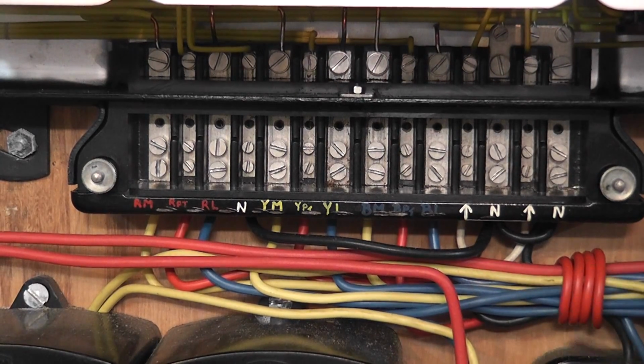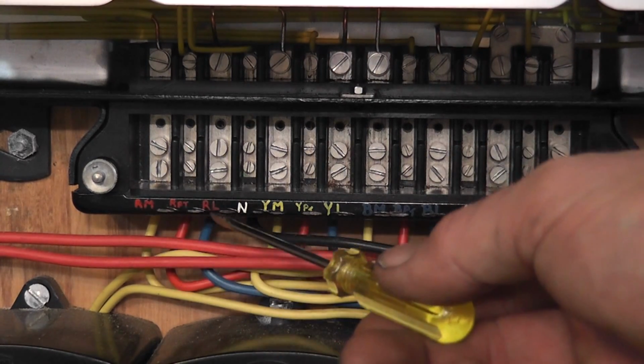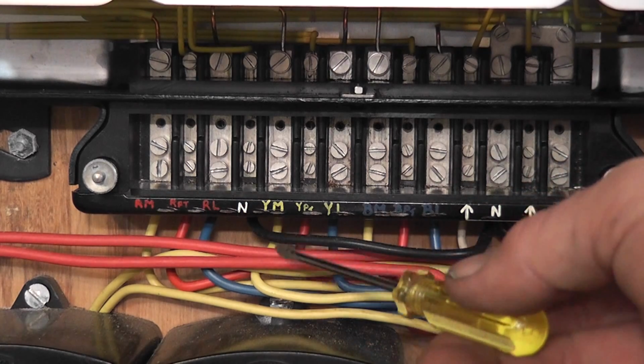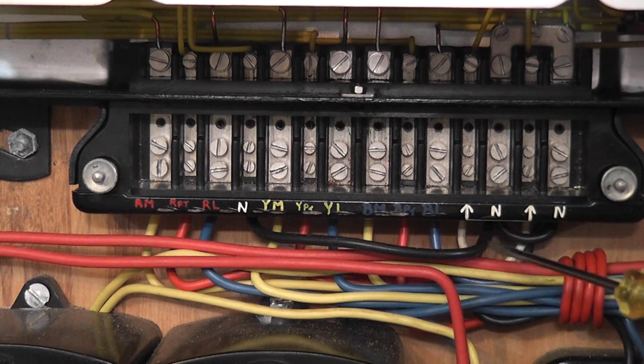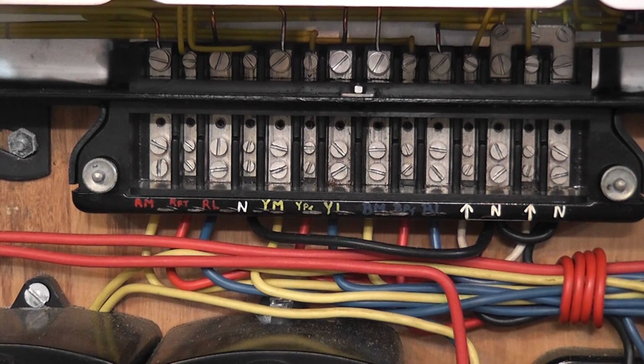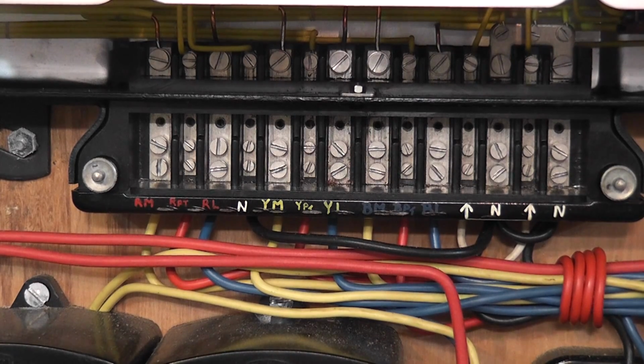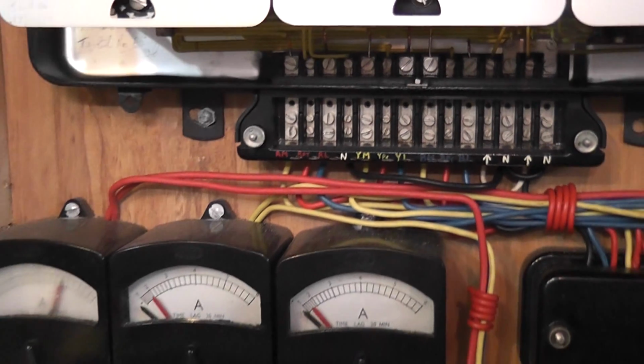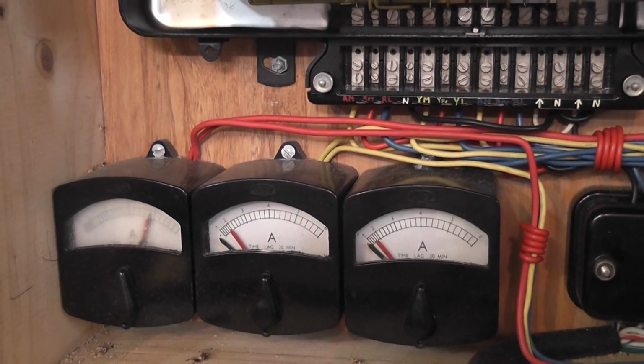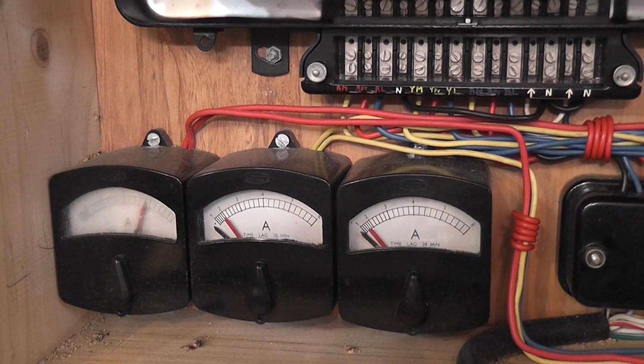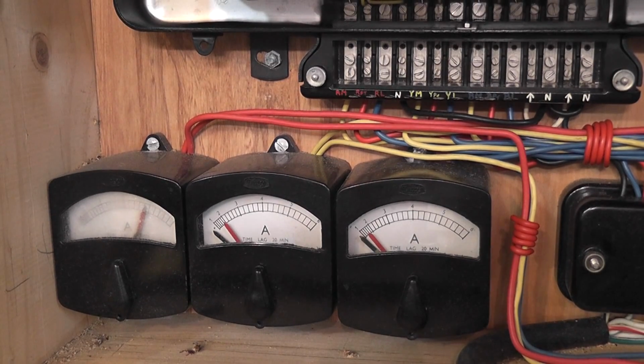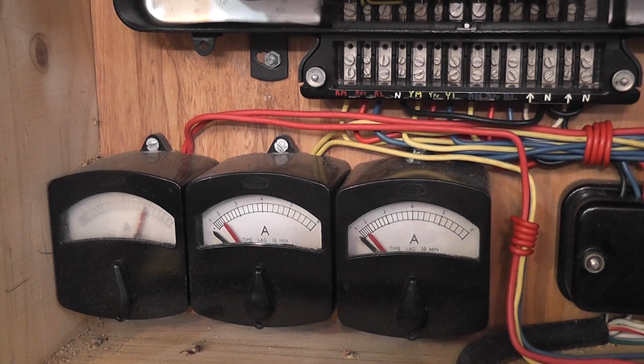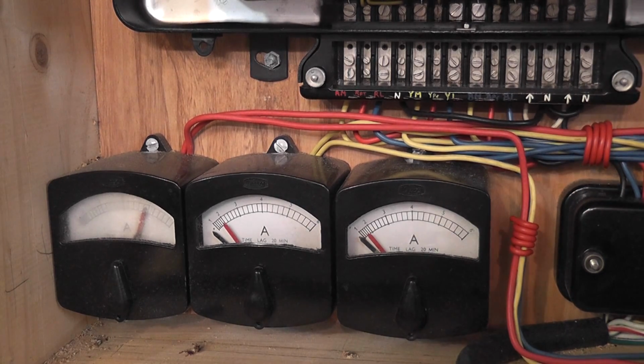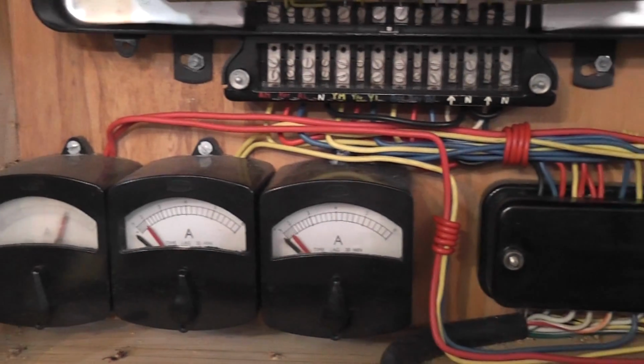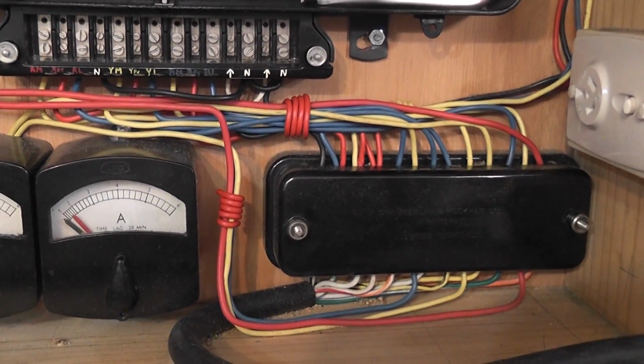Test terminal block is standard, current in, potential in, current out, red phase, yellow, blue phase, and a couple of jumpers for neutrals and auxiliary control points. Also, 3 MDI meters are fitted, which don't really matter about the power factor as such. MDI maximum demand indicator readings, and a test block is on this side of the device.